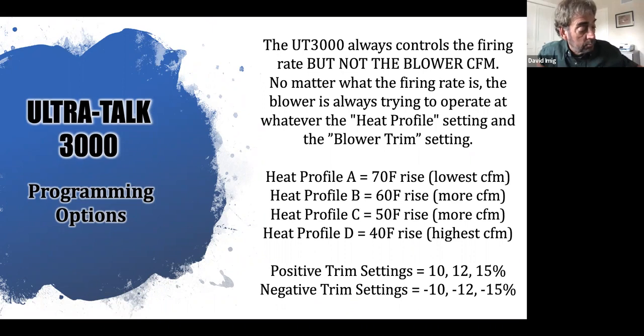So they'll give you some parameters. In this case, they give you a couple, and you go to the thermostat to work with that blower CFM based on the zoning and the sizes of your zones. It'll give you the ability to change the CFM operation to a degree. Here are the profile settings, and what this is dealing with is temperature rise, and that's how they're going to control that blower based on the stage you're in, regardless of where you'd like it to operate. So you can select one of those temperature rises, and if you're trying to lower the CFM to a minimal, you're going to want to select the 70, or the highest degree of rise, to get the lowest CFM. The other setting is the positive or negative trim settings.